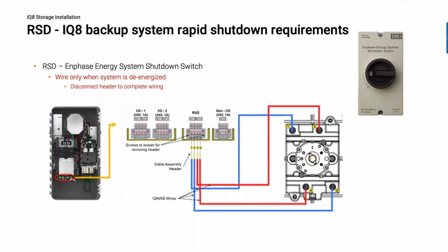But remember, the inverter's job and capability is to actually produce power if the grid fails. So what happens is that if you flip a big blade switch, those inverters still produce power. And so those conductors from the rooftop down to the ground are still potentially live with electricity. And so it doesn't comply with rapid shutdown rules.